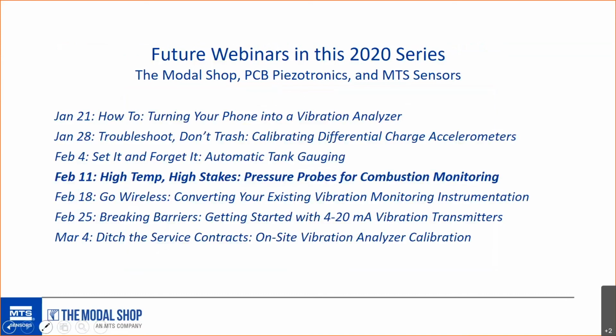How to turn your smartphone into a vibration analyzer. New technology in the vibration market in general. You can connect a digital accelerometer directly to your smartphone, and you're really only limited by the app that you buy. There's a variety of apps out there that give you a basic vibration measurement, or you can go with an app that I have on my phone that really gives you everything you would get with a portable vibration analyzer. You can choose your window, you can choose your resolution, frequency, almost anything you can do with a portable vibration analyzer, you can do on this app. It's breaking down some of the barriers to starting a vibration monitoring program, or at least taking some vibration data by using your phone as the piece of instrumentation that does the data acquisition.